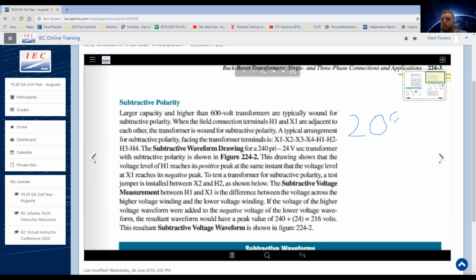277, 208, right. So what I meant by that, and I wasn't very clear, let me be more clear. 32 buck, or a subtractive number, 32 from 240 would be 208. We're going to get into that in just a second. Or in this case, 240 with a 24 volt buck transformer would be 216 volts.